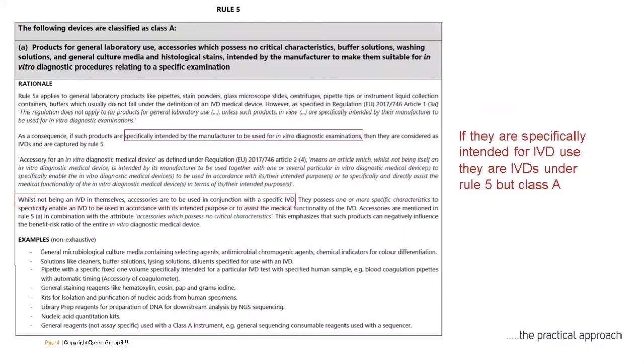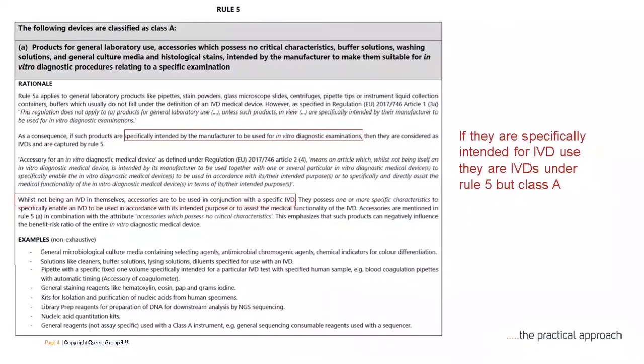So a little bit of a change in the accent between the IVD directive and the IVD regulation, but it clearly puts them in scope if they're specially intended for IVD applications under Rule 5, at which point they become Class A devices. So let's just flip and look at the research use only products. If you're an IVD, then you're either an IVD product or a product on its way to being an IVD in its performance evaluation.